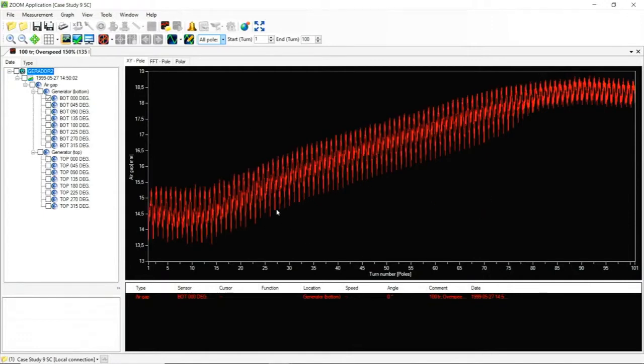At this point, the rotor is under overspeed. If I put the cursor on, you'll see it's rotating very fast. If you look at the speed down here, that's 139 RPM. Remember, nominal is 90, so it's 49 RPM above normal, about 154-155%.